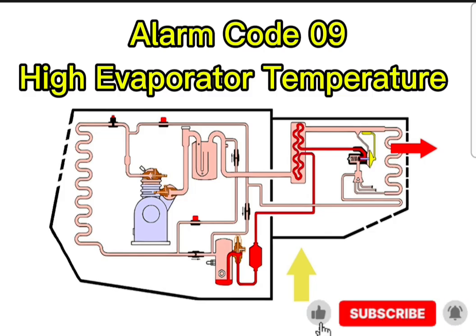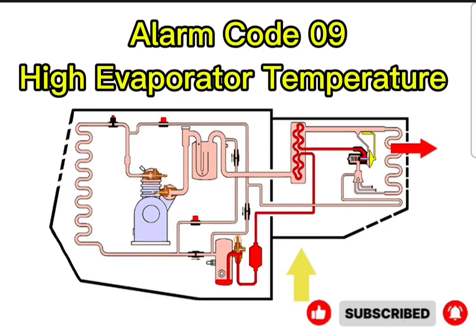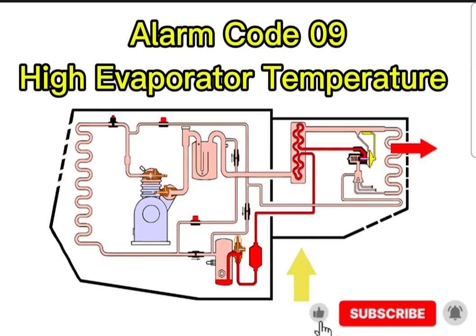During a programmed defrost cycle, the system triggers the hot gas solenoid. And what exactly is that? A solenoid is just an electromechanical valve, an electromagnet that pulls a plunger to open a pipe. When it opens, it acts as a bypass. Okay. Instead of sending that scalding, high-pressure refrigerant gas outside to vent its heat, it reroutes that 200-degree gas directly back into the frozen indoor evaporator coils. It turns the freezer into a blast furnace for a few minutes to violently melt the ice. Exactly. And once the ice is gone, the solenoid is supposed to close, and normal cooling resumes.